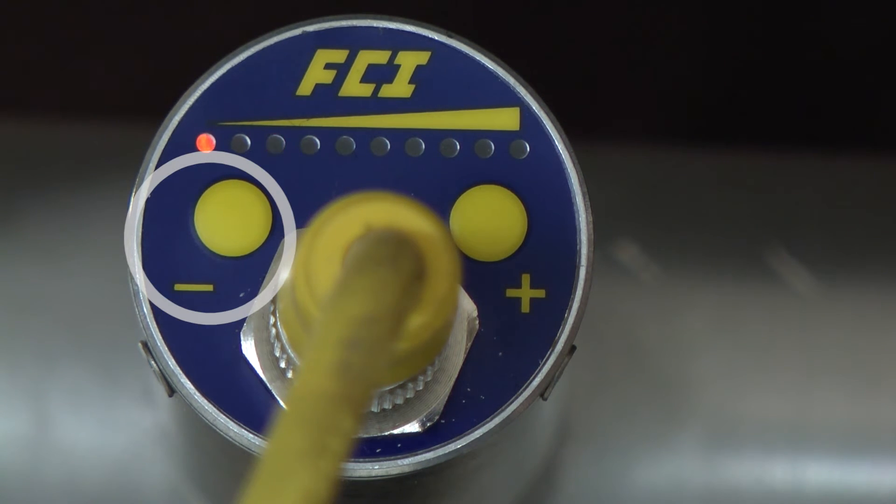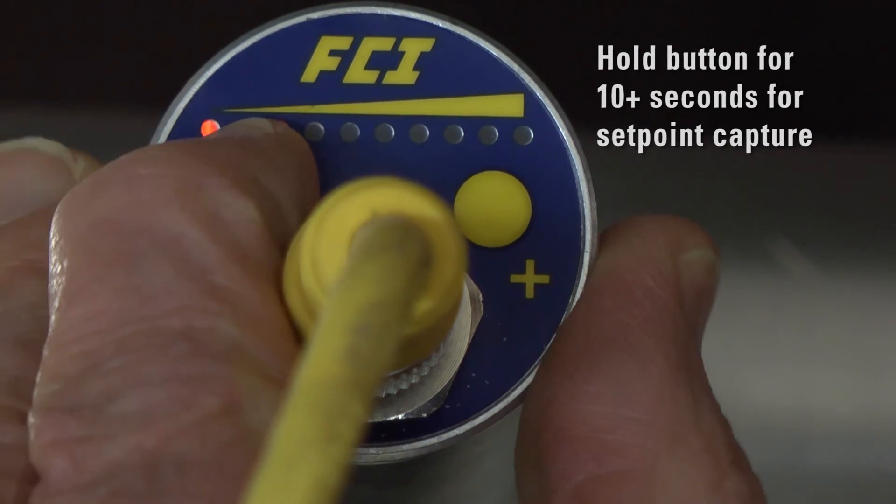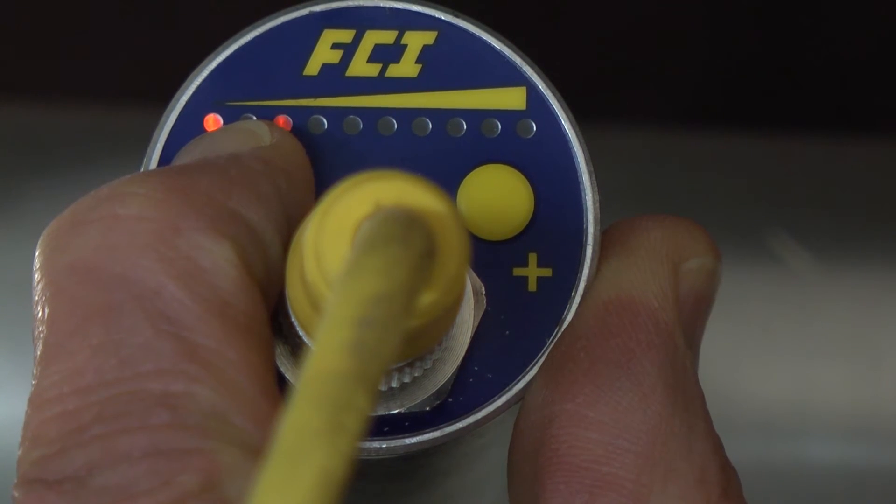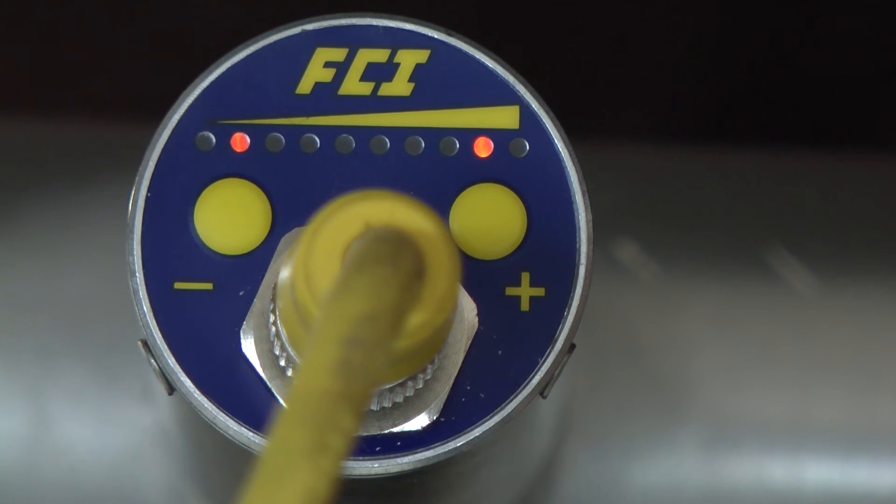Press and hold the minus button for at least 10 seconds to enter into this range setting mode. Keep pressing through the capture setpoint LED pattern—a unique LED pattern will emerge. The first and last three LED sequence indicates entry into this range capture mode.